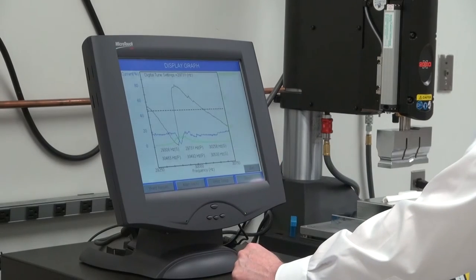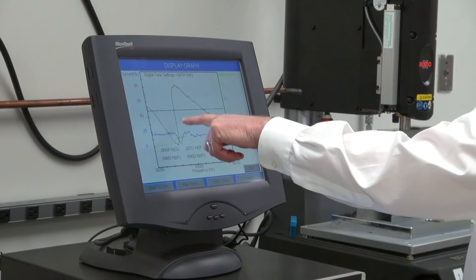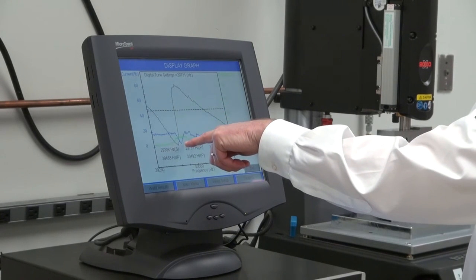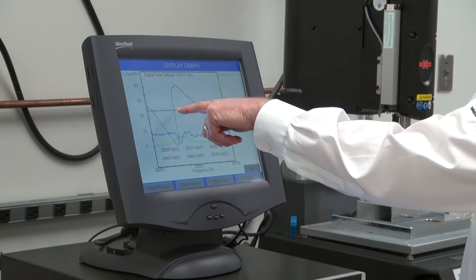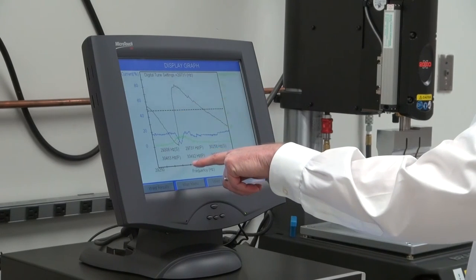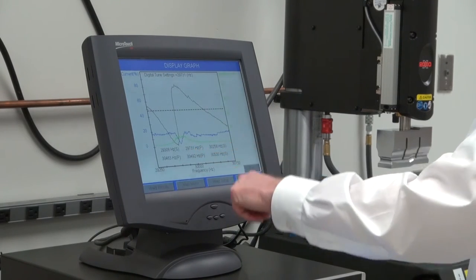Let me display the graph. It'll show me a graphical image of the scan. Right here is where we have the maximum impedance. We have the minimum current, and we have a crossover phase right here, zero right here, and that's going to be the parallel frequency. That is 29.731 kilohertz.